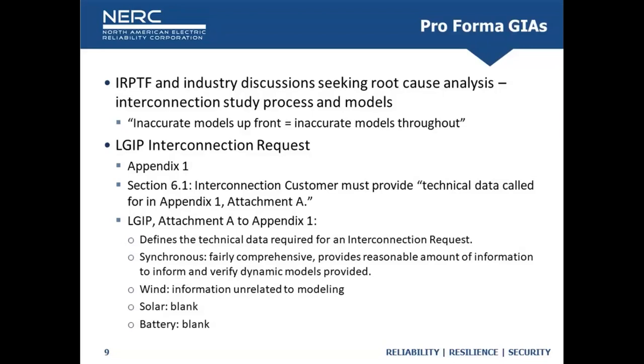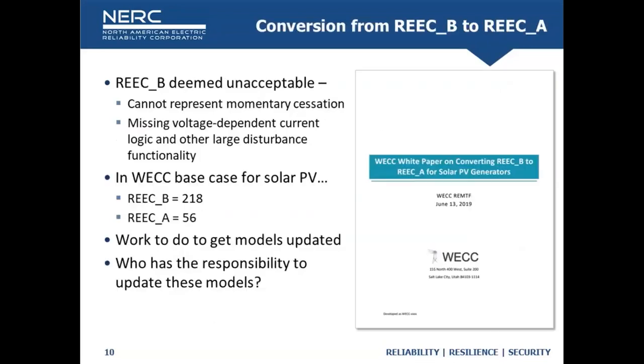And I think that might be leading to some of the challenges that we're facing as an industry to get very accurate models right up front, at least during the trial operation, the commissioning process into the commercial operation time. We understand there are limitations in the model, expected model settings and things like that during the system impact studies and the feasibility studies, et cetera. But once that unit is commercially operational, we know what the equipment is set at in the field. And I think that the models are just not getting updated as they should be.